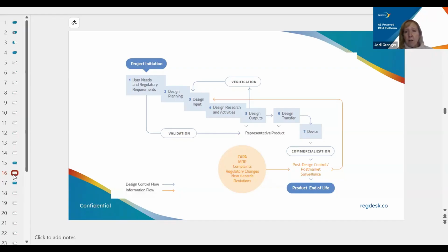And from there, the project will go through multiple phases where you're doing feasibility testing until you get to the point where you can do full-blown verification and validation testing. Ultimately, once all your verification and validation is completed, then you can work to move to a design transfer into the manufacturing space. And once you've commercialized the product, all of the activities, the complaints that you receive, the deviations that might be found in your production process, all of those will play into the changes that you may make over your product life cycle.